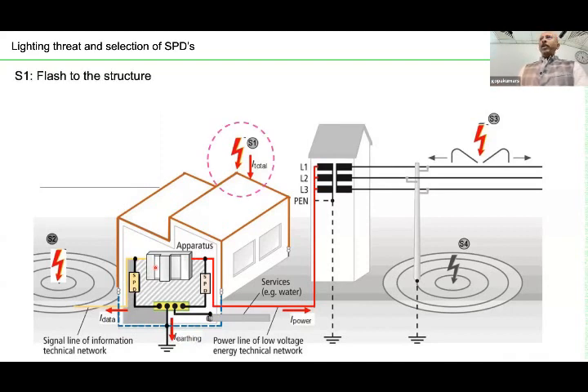Now, what kind of protection do you need? You need protection in a typical building. You need protection from source S1, which is a direct lightning strike on the building. That means your building should have an external lightning protection system.